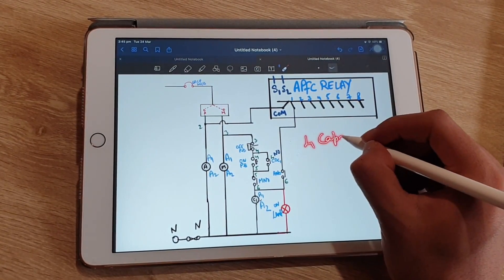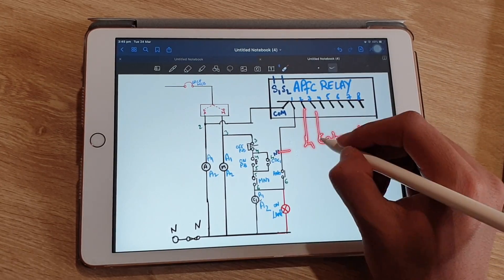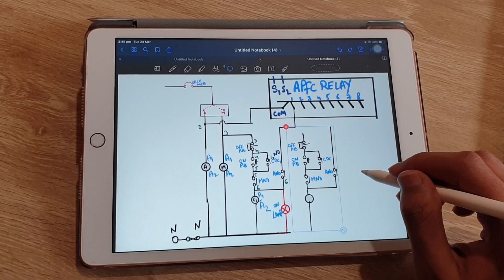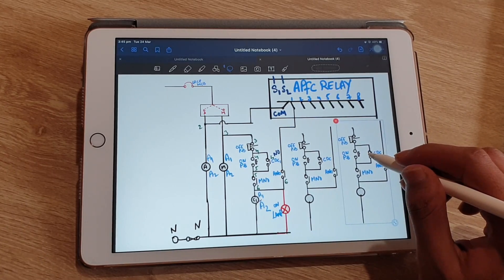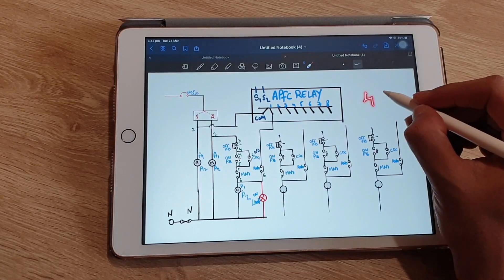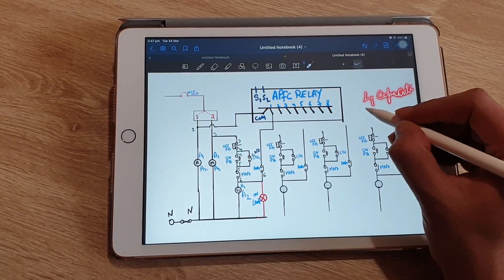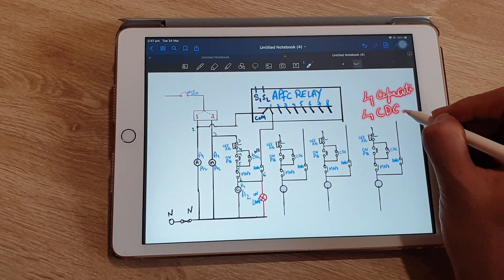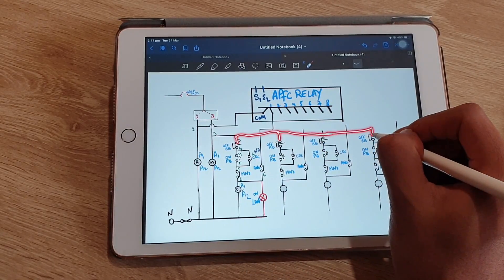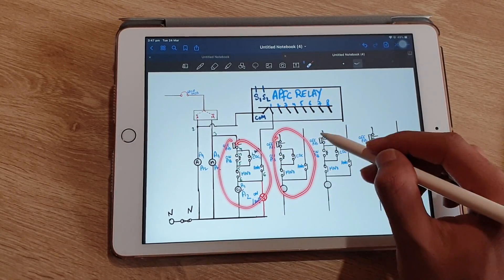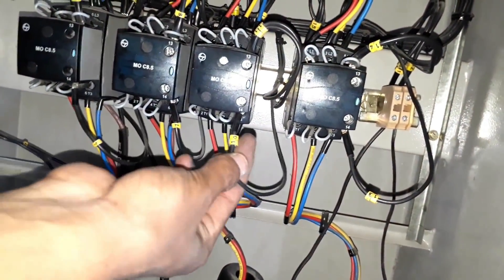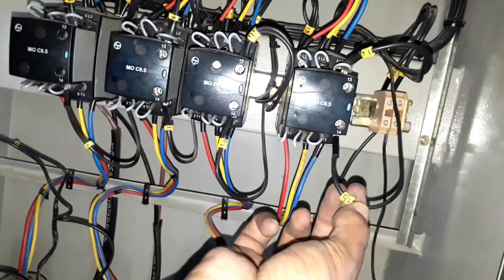For example, if I am using four capacitors in this panel I have to use four CDCs. For four CDCs I have to use four of these setups, and I can loop these four setups via off push button terminal number three. You can see here in this panel I am using four capacitor duty contactors.